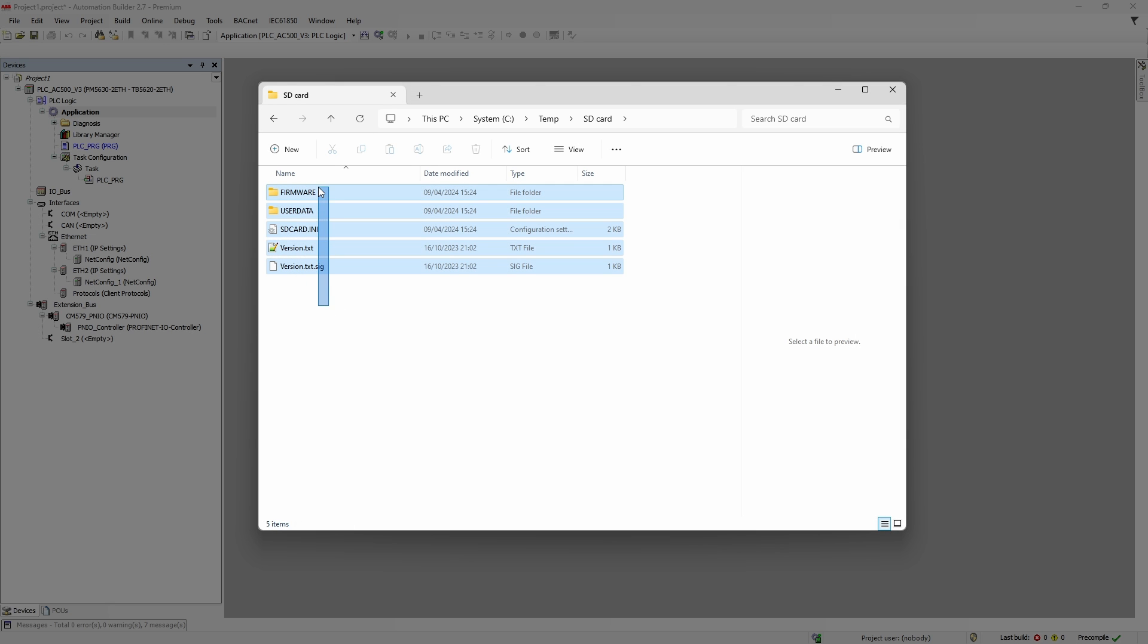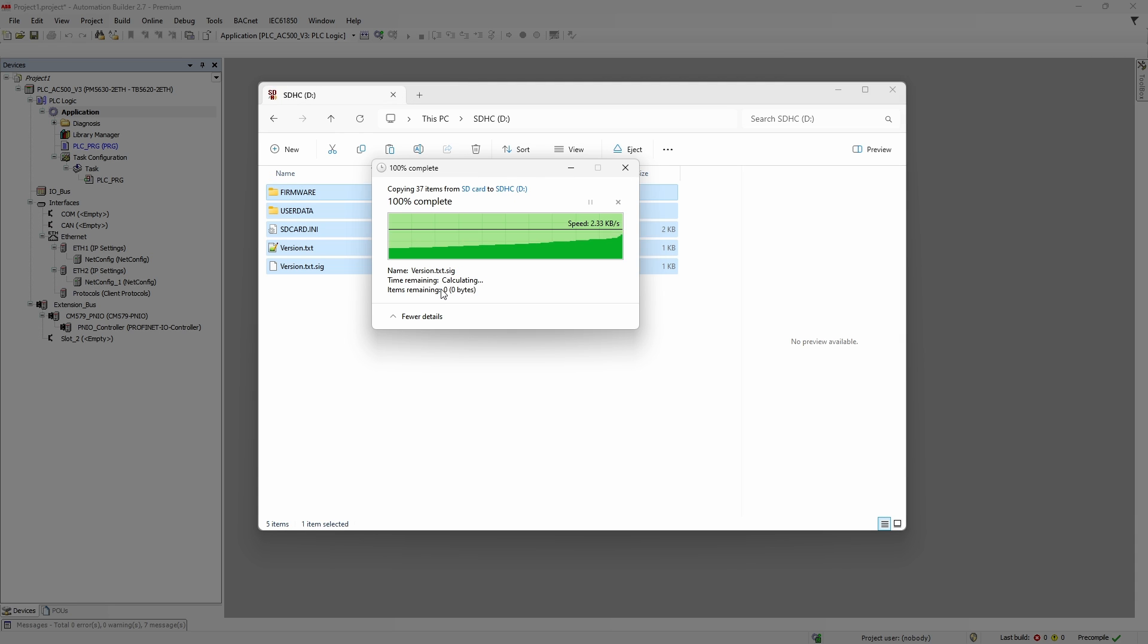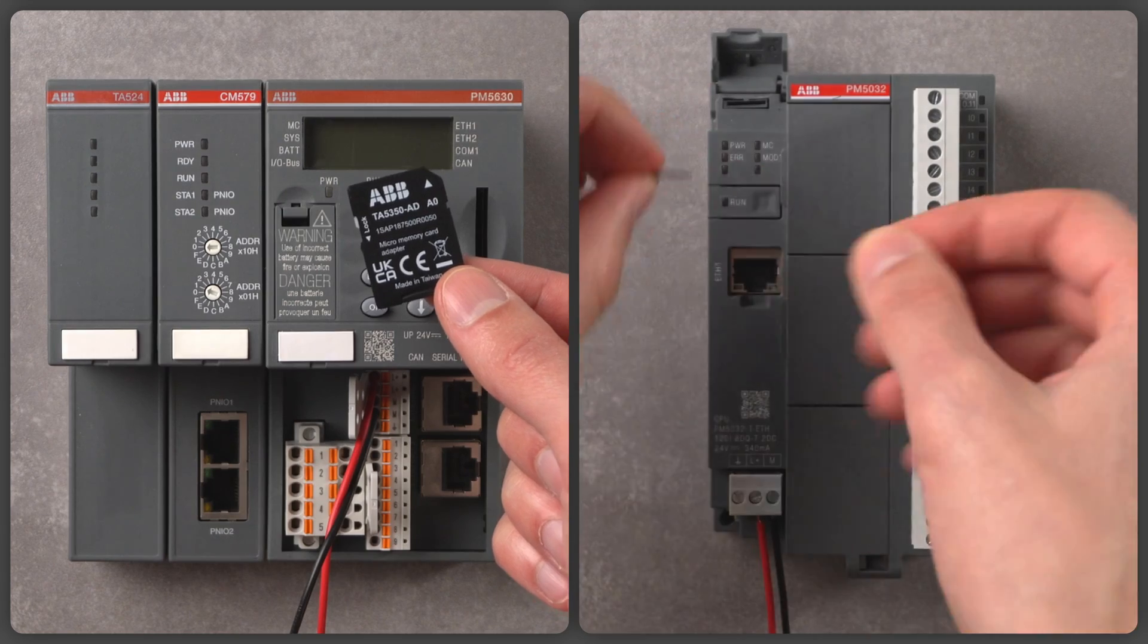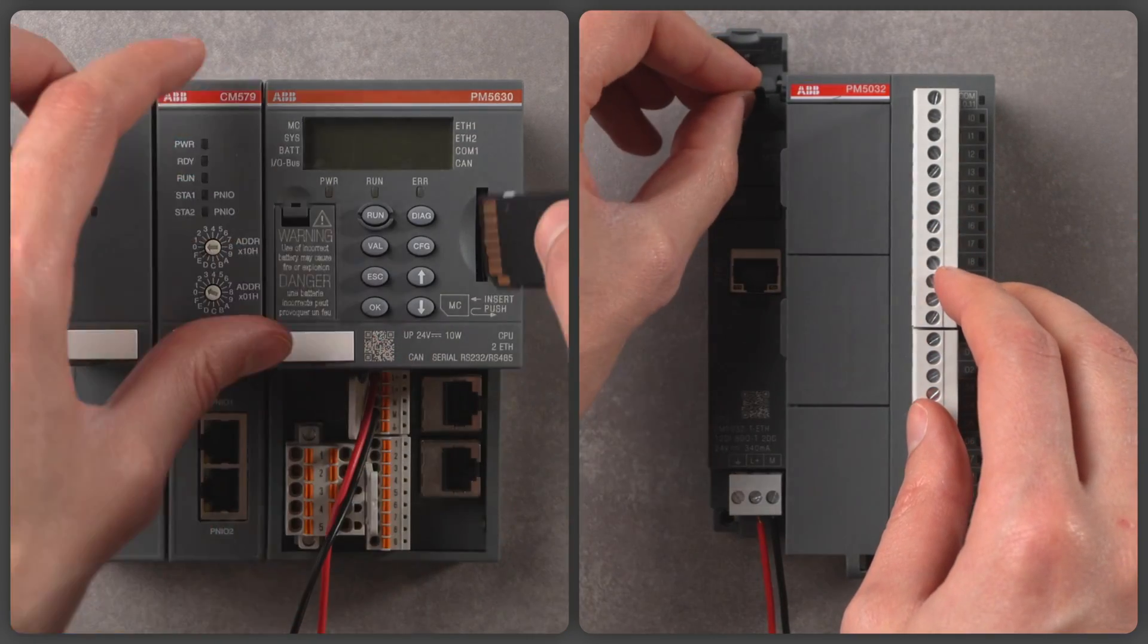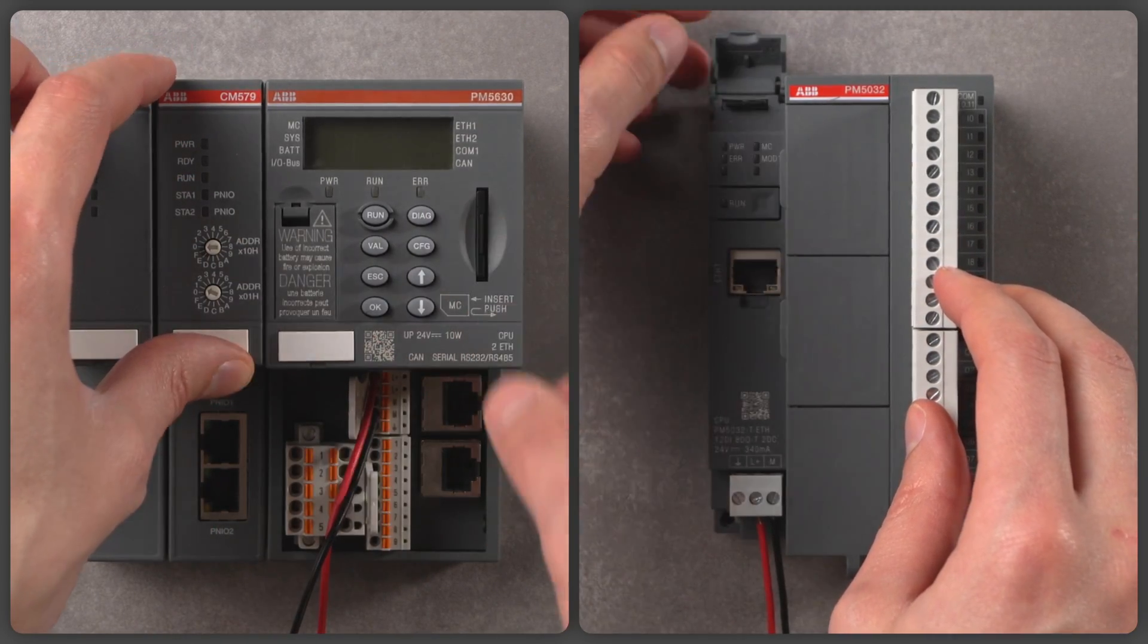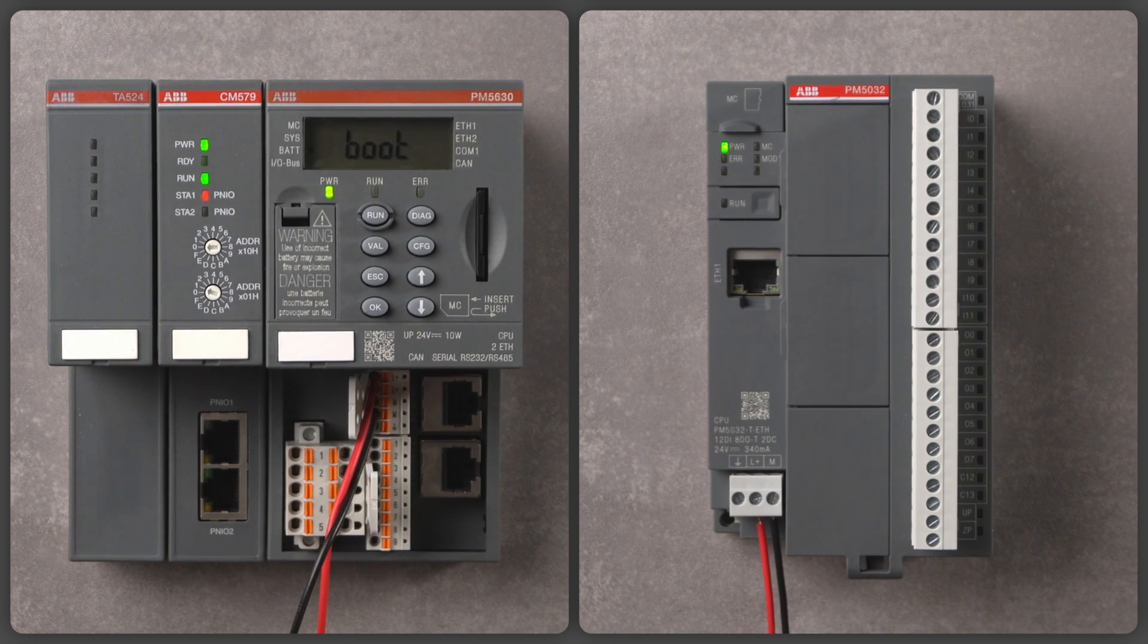Now we can close the file, select and copy all files and folders in the same level as SD card INI and paste them to the root folder of the memory card. Once that is finished, we take the memory card to PLC, put it in and turn the power on. The update process will start.